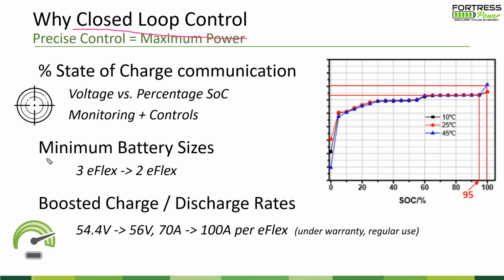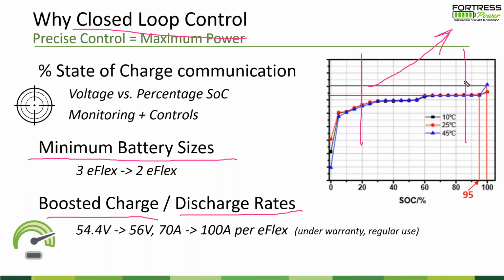Another advantage of closed loop communication is that you can reduce the minimum battery size, because you get boosted charge and discharge rates. In that middle range of the battery, it's okay to charge a little faster as long as you can slow it down at the end. So closed loop communication allows us to charge at a slightly higher voltage and faster rate.